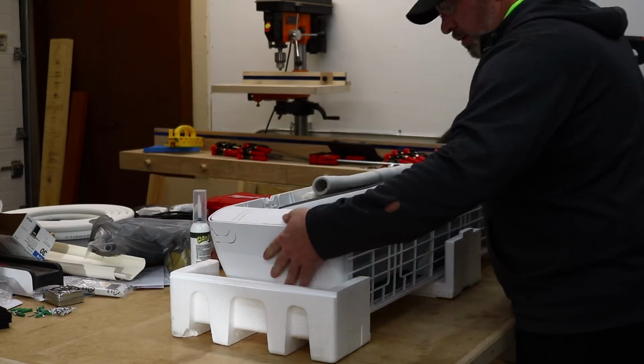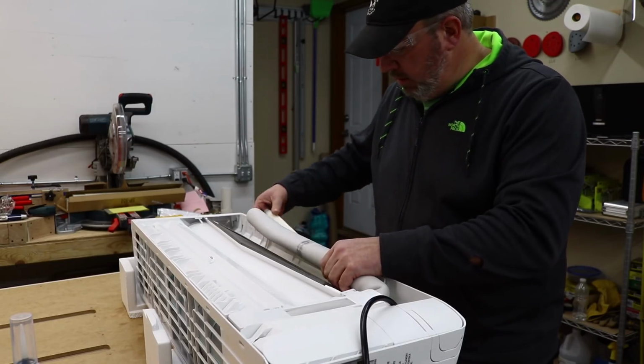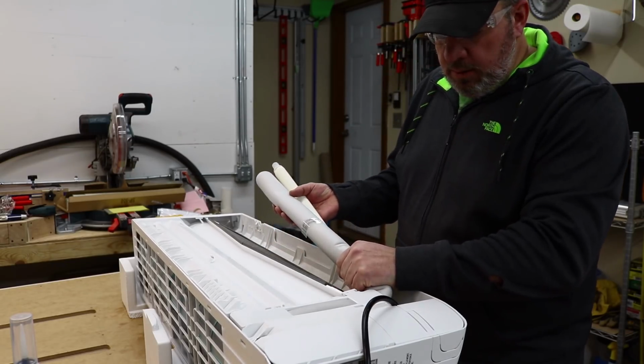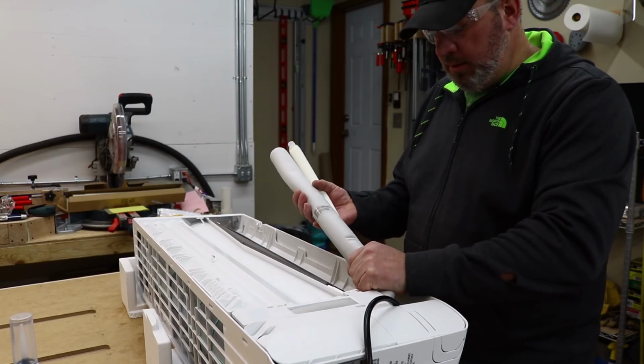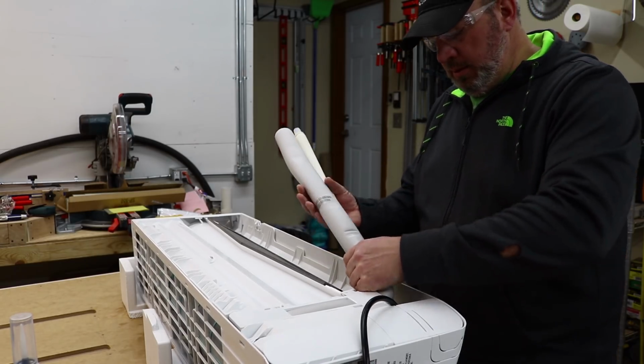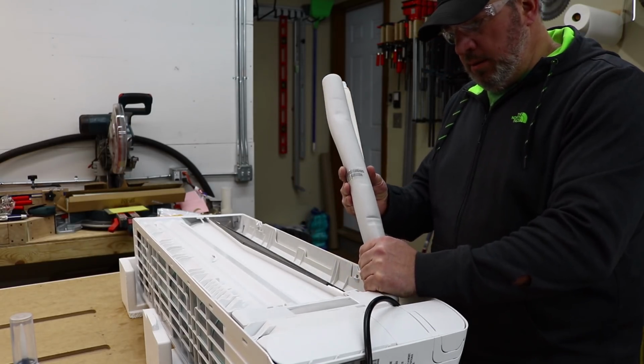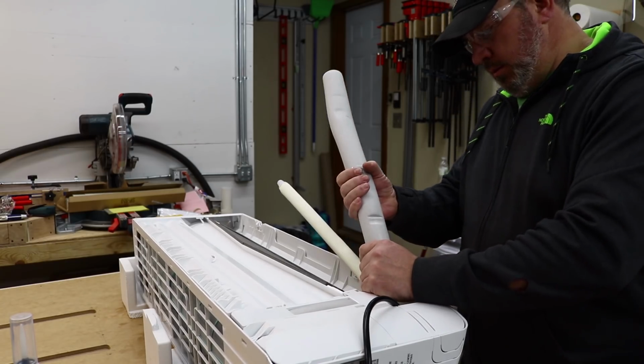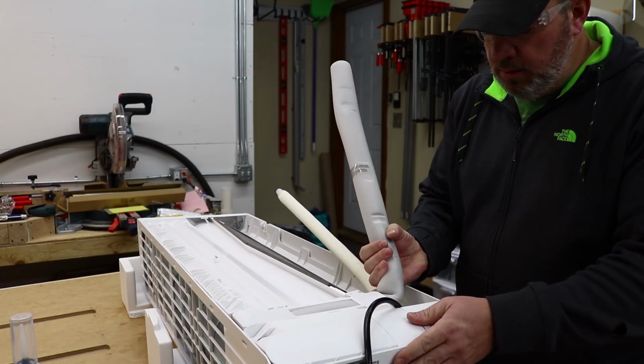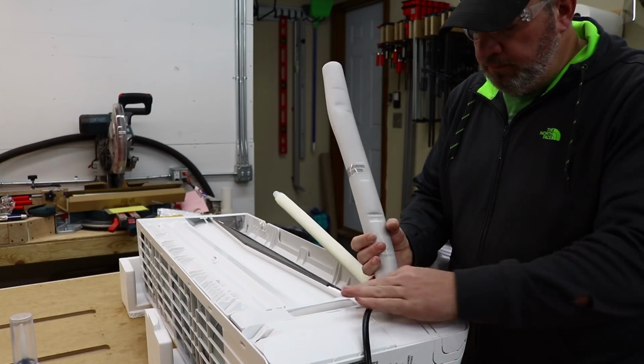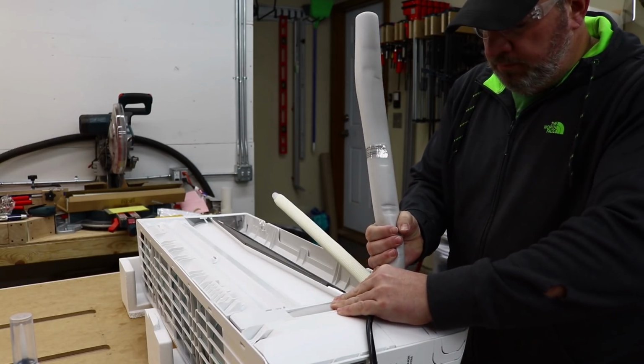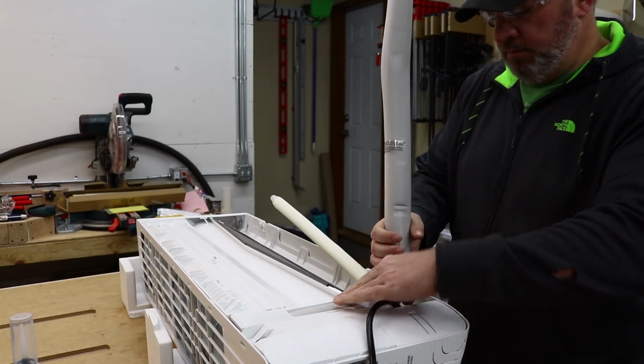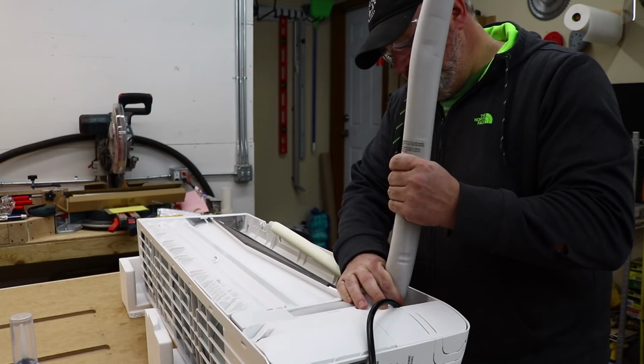It was now time to permanently mount the inside unit. I flipped the unit on its back and very slowly and gently pulled the copper lines away from the unit and angled slightly downward to match the angle of the hole I drilled earlier. Based on the number of warnings in the manual not to kink these pipes, I came to believe that if I did, the entire world would explode and we'd all die. But seriously, don't kink the pipes in bending them.